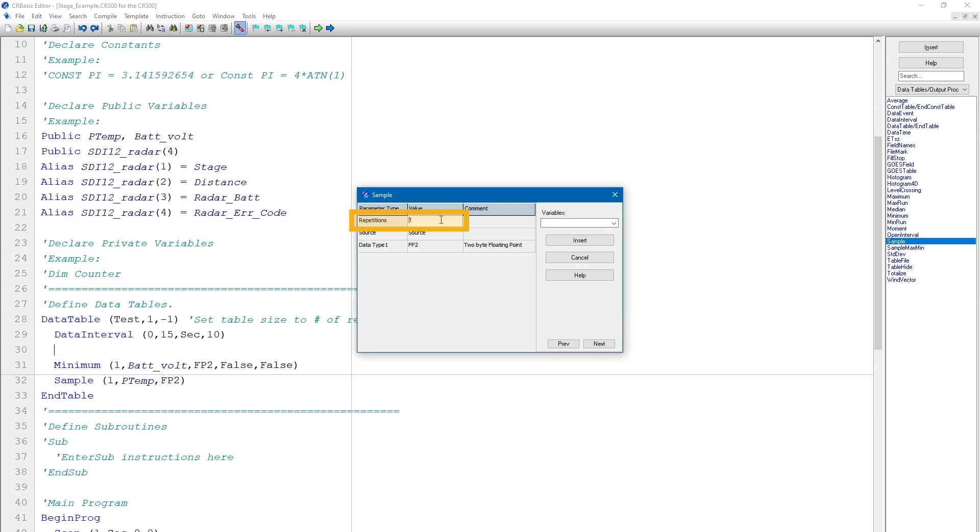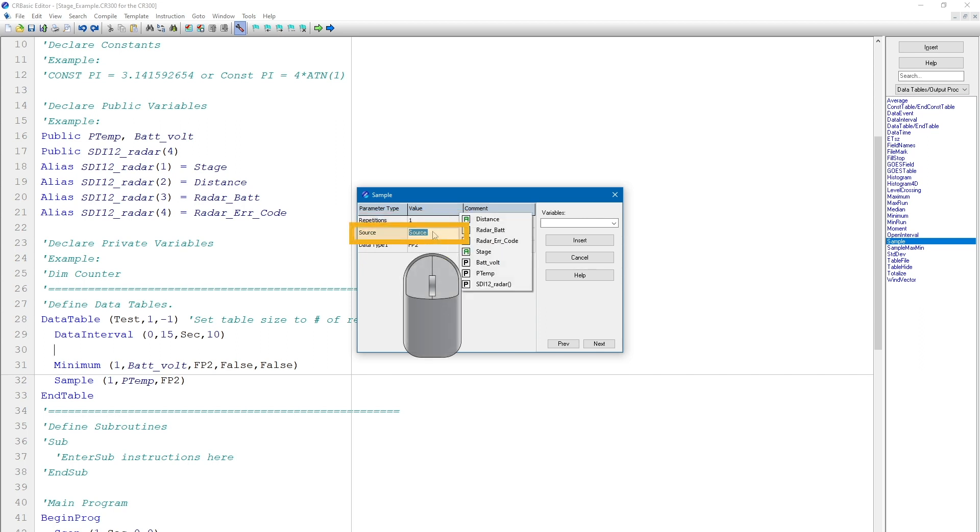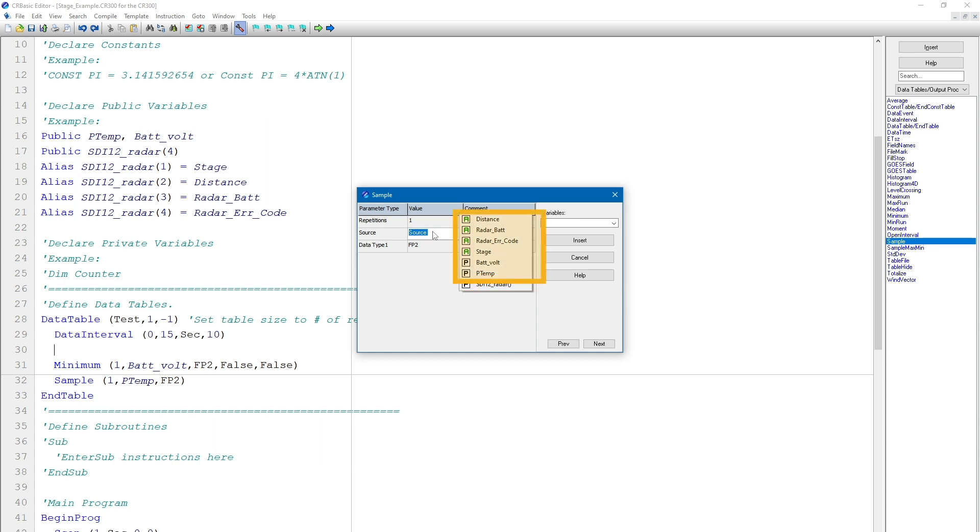I will leave the repetitions parameter at 1 as I am only interested in recording the stage value. If I wanted to record all four values output by the sensor, I could change the repetitions to 4. I can right-click in the source box to bring up a list of variables available to be used in this instruction. Notice this list includes both the original SDI-12 radar variable and the aliases for each variable in this array. In this case, the source is stage, so I will click on stage.